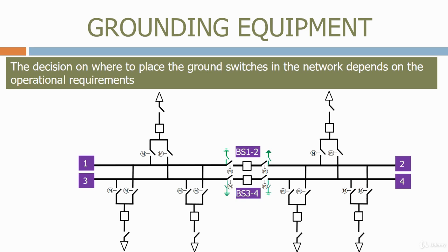We need to be able to maintain all of the incoming and outgoing cables to the substation. We therefore need to provide feeder ground switches. Circuit breakers need periodic maintenance, so we need to be able to ground the conductors on both sides of the circuit breaker. So let's provide circuit ground switches. This is probably the minimum requirement for ground switches on this type of substation, but depending on the utility's permit requirements, additional ground switches may be provided.